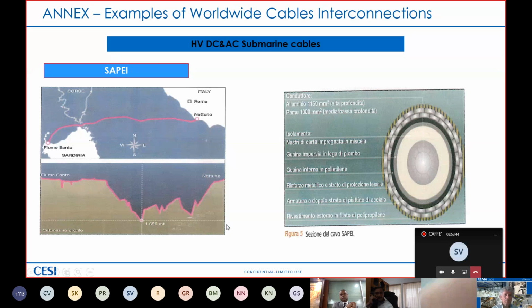This is the path from Sardinia to the Italian peninsula. In this first part, the cable is different, a so-called low depth cable. This one is the picture of alta profondità, which means high depth. The cross section is smaller for medium to low depth, and it is copper. The cross section is higher, and it is aluminum for the high depth. So here on the first part, you have the low depth cable. Then you reach 1,650 meters below sea level. Here it's aluminum cable, and here again we come to copper cable. So when you change the material, you have to imagine transition joints, another weak point for sure.